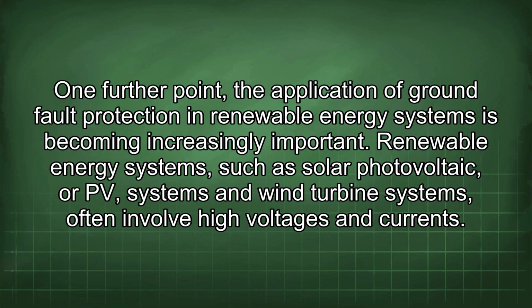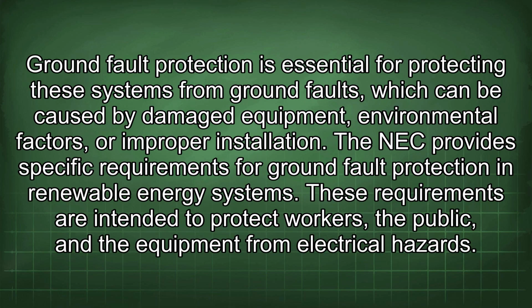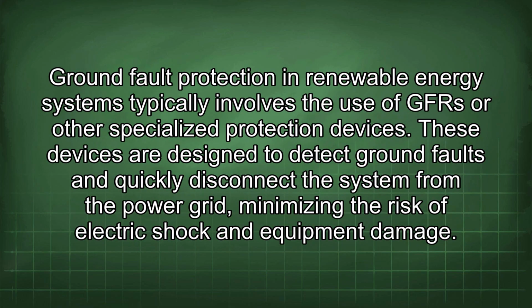One further point: the application of ground fault protection in renewable energy systems is becoming increasingly important. Renewable energy systems, such as solar photovoltaic or PV systems and wind turbine systems, often involve high voltages and currents. Ground fault protection is essential for protecting these systems from ground faults, which can be caused by damaged equipment, environmental factors, or improper installation. The NEC provides specific requirements for ground fault protection in renewable energy systems. These requirements are intended to protect workers, the public, and the equipment from electrical hazards. Ground fault protection in renewable energy systems typically involves the use of GFR or other specialized protection devices. These devices are designed to detect ground faults and quickly disconnect the system from the power grid, minimizing the risk of electric shock and equipment damage.